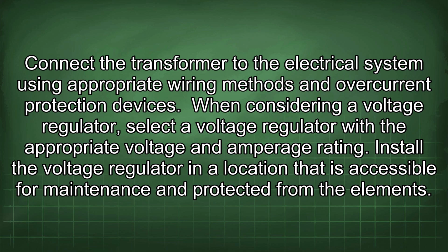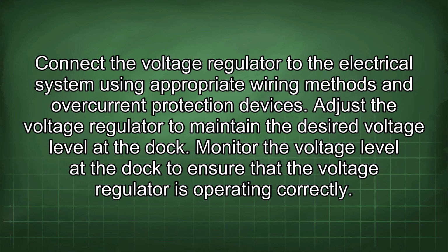When considering a voltage regulator, select a voltage regulator with the appropriate voltage and amperage rating. Install the voltage regulator in a location that is accessible for maintenance and protected from the elements. Connect the voltage regulator to the electrical system using appropriate wiring methods and overcurrent protection devices. Adjust the voltage regulator to maintain the desired voltage level at the dock. Monitor the voltage level at the dock to ensure that the voltage regulator is operating correctly.